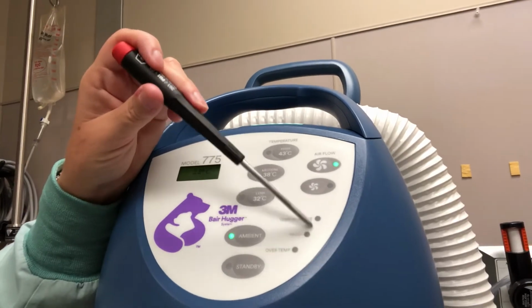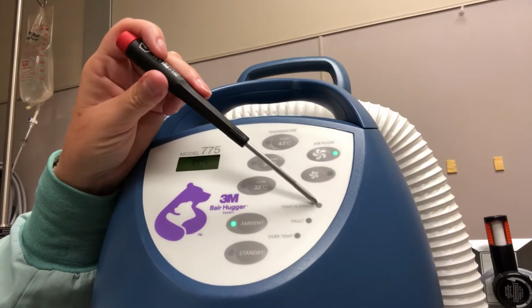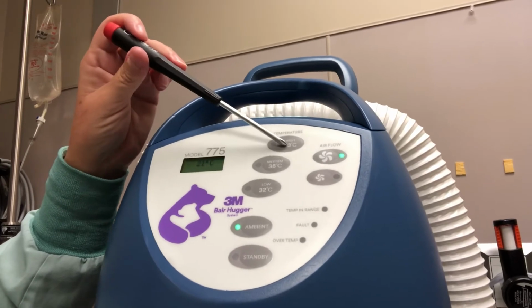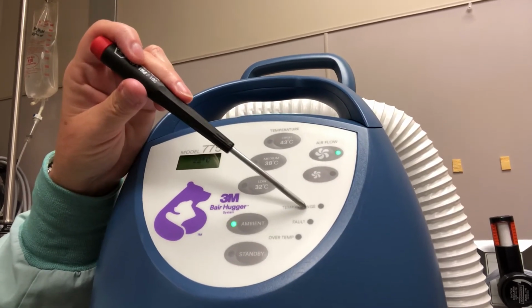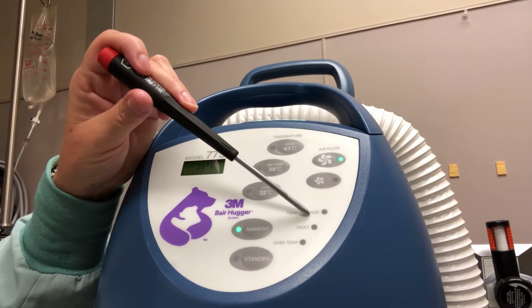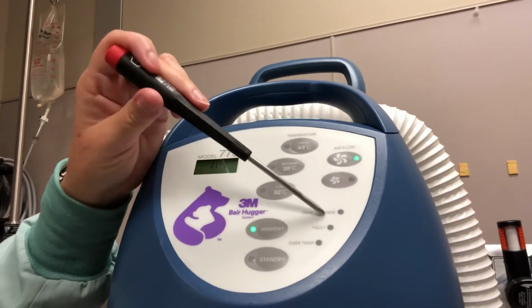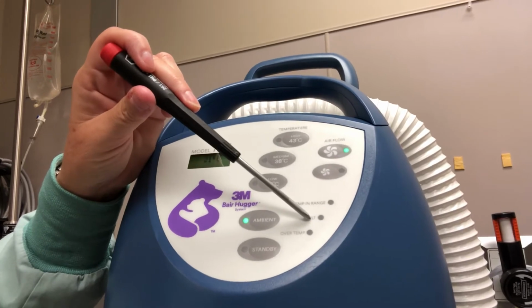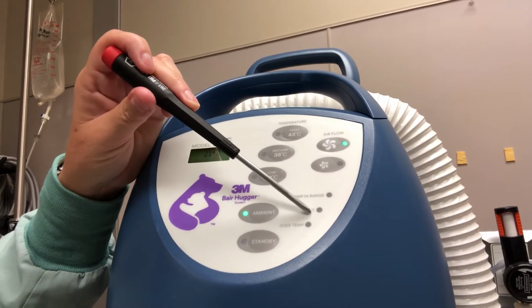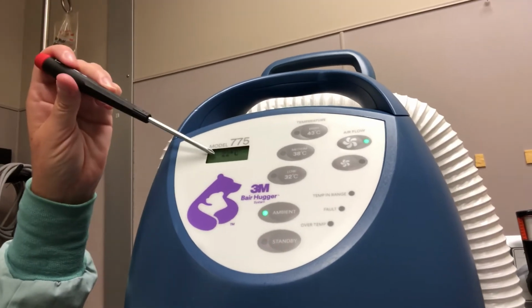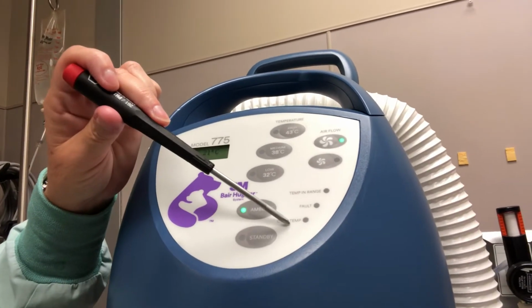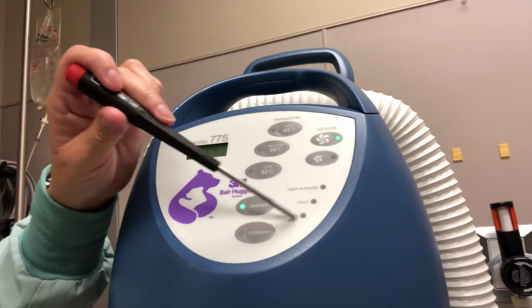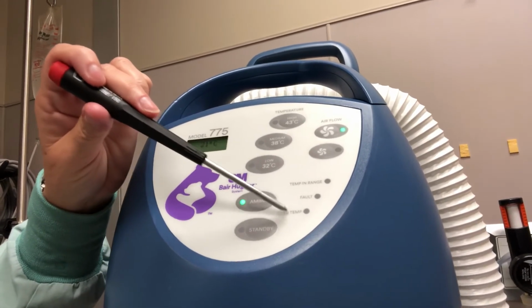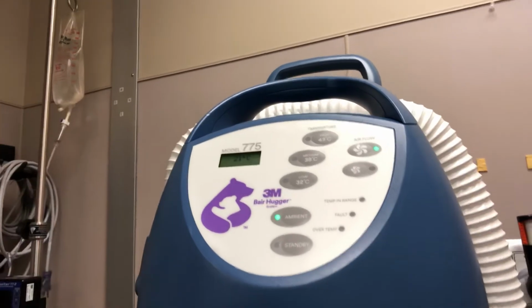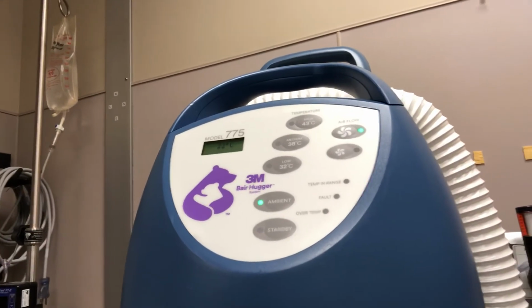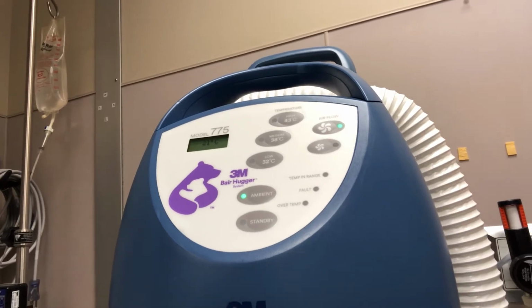Now over here we have some indicator lights. We have temperature in range. So when we select one of these temperatures, this light will come on when it gets within 3 degrees plus or minus of the selected temperature. We have our fault indicator. So anytime there's any electrical faults, this will light up and we'll see a fault code on the screen. And then we have our overtemp indicator. So if it gets between 46 and 56 degrees Celsius, this will light up, the unit will turn off, and we'll see an overtemp error. And the alarm will continue until the unit's unplugged.